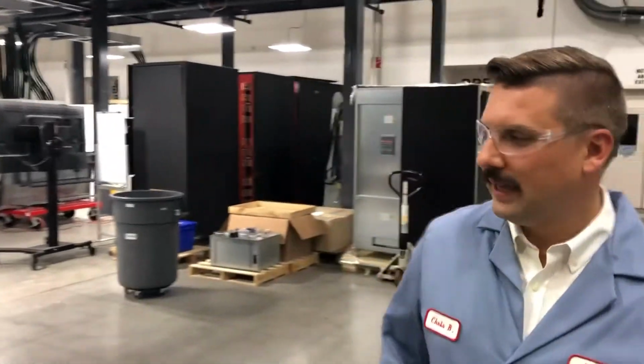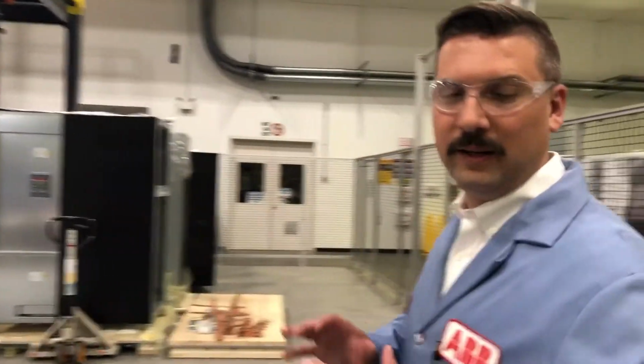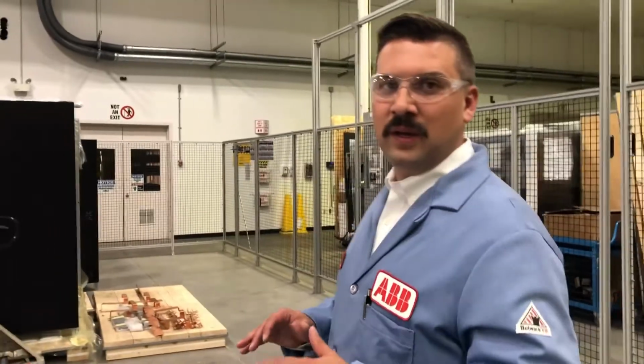As we head over to look at what the guys are working on, I'm going to tell you a little bit about the lab's capabilities. We have four 1.6 megawatt test bays. We have the capability to test three 1.6 megawatt UPS systems in parallel or standalone, or we can test four 1.2 megawatt UPS systems in parallel or standalone.